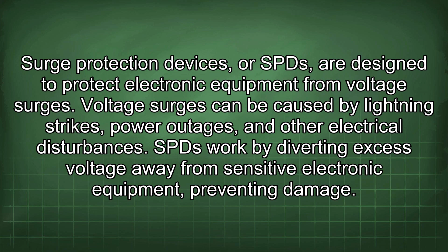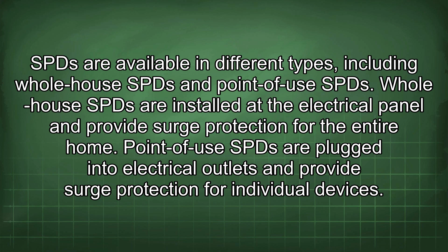SPDs are available in different types, including whole house SPDs and point of use SPDs. Whole house SPDs are installed at the electrical panel and provide surge protection for the entire home. Point of use SPDs are plugged into electrical outlets and provide surge protection for individual devices. When choosing an SPD, it's important to select one that's rated for the voltage and current of the electrical system. It's also important to choose an SPD that's listed by a recognized testing laboratory.